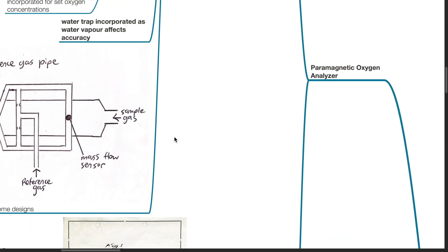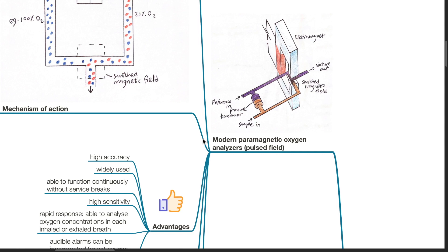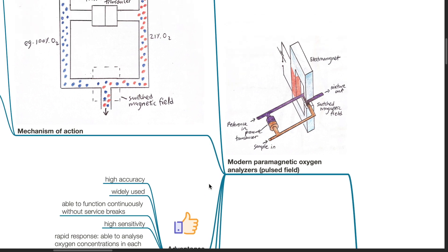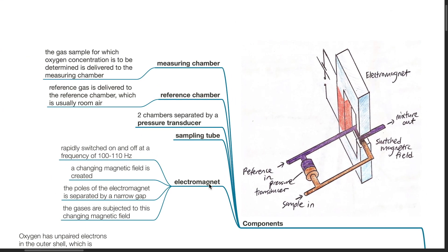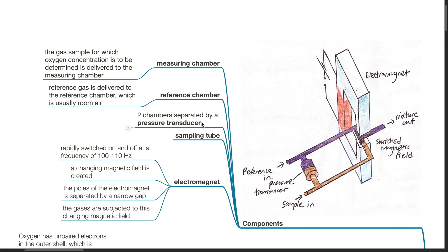The modern paramagnetic oxygen analyzer has components including a measuring chamber, reference chamber, pressure transducer, sampling tube, and electromagnet. The gas sample for which oxygen concentration is to be determined is delivered to the measuring chamber, while the reference gas — usually room air — is delivered to the reference chamber. The two chambers are separated by a pressure transducer.